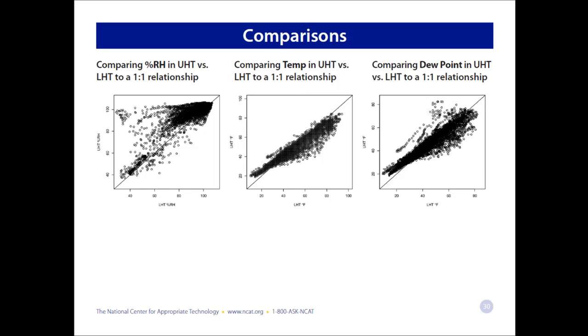The comparison of temperature in the second graph, or the middle graph, reveals the trend that the upper high tunnel was cooler than the lower high tunnel, with numerous points below the one-to-one relationship line, with an exception at the lower temperatures, where the upper high tunnel is a little bit warmer than the lower high tunnel. And this result was pretty unexpected, but considering that the heat recovery ventilation system was controlled by an external thermostat that shut it down below 35 degrees to keep the condensate line from freezing, it's not very surprising that we don't see the heat recovery ventilation system performing at the lower temperatures, because it was shut down.